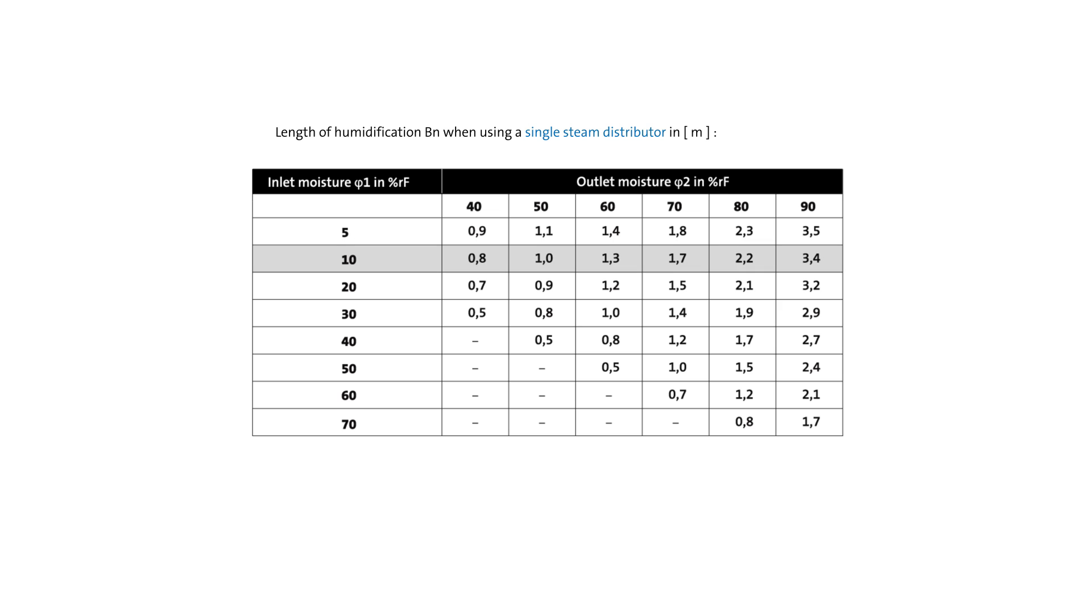If the relative humidity of the inlet air amounts to 10% relative humidity and the required relative humidity of the outlet air is 50% relative humidity, a humidification distance BN of 1 meter must be maintained.